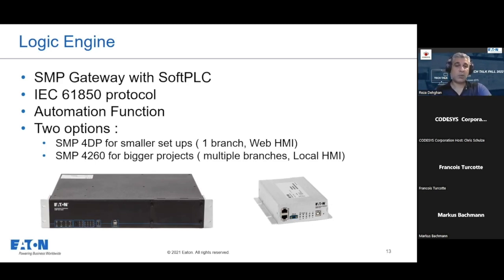And then we offer two different options based on the two different models that we have with SMP Gateway. The left one, the bigger box, that is SMP 4260 for bigger projects. It supports multiple branches of transformers with a local HMI. Basically, you can connect a screen to the back of the box and you will get the single line diagram on the screen. And for smaller projects, SMP 4DP, the smaller box, the one on the right side, that supports only one branch of transformers, up to 8 transformers.